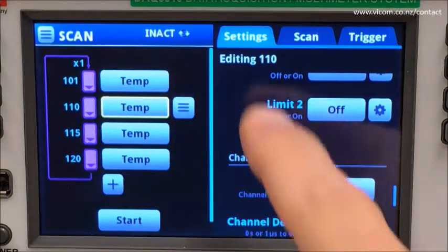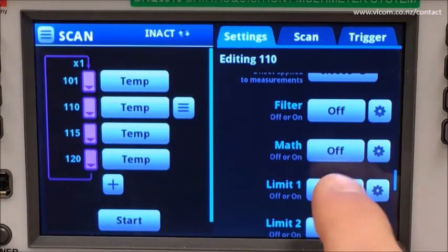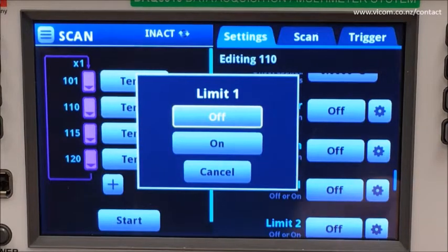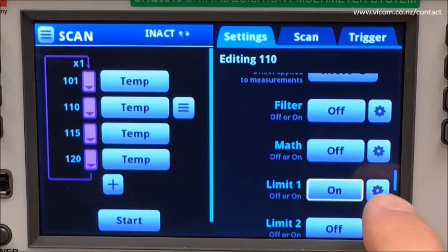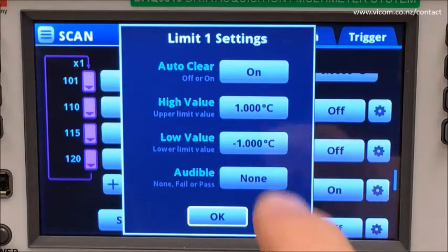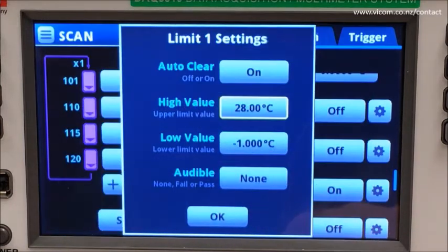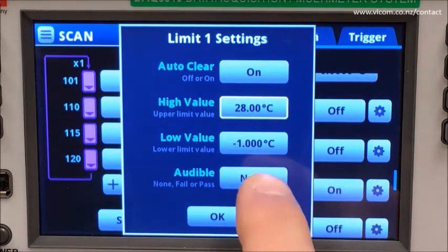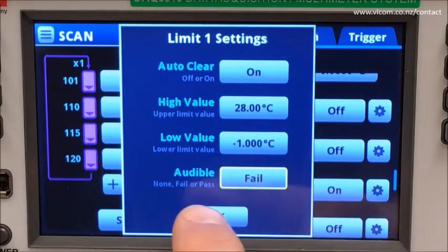Channel 110 is monitoring a microprocessor, and it has a tendency to get hot. Let's provide ourselves a notification if something goes wrong and we hit that condition, so I will establish a limit. I will set a high value of 28 degrees C, and if my back is turned, I want to hear if the limit has been exceeded.